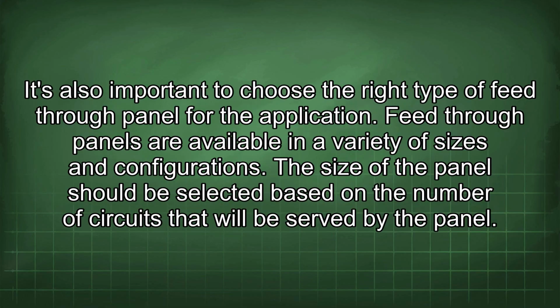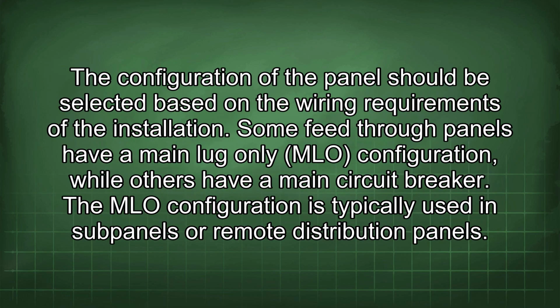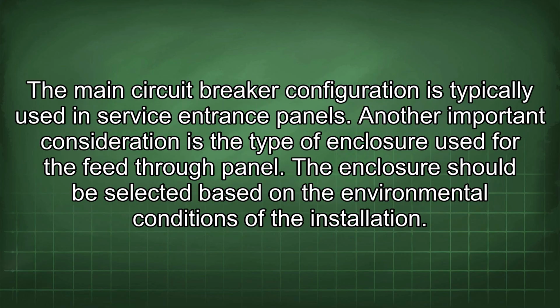It's also important to choose the right type of feed-through panel for the application. Feed-through panels are available in a variety of sizes and configurations. The size of the panel should be selected based on the number of circuits that will be served by the panel. The configuration of the panel should be selected based on the wiring requirements of the installation. Some feed-through panels have a main lug-only (MLO) configuration, while others have a main circuit breaker. The MLO configuration is typically used in subpanels or remote distribution panels. The main circuit breaker configuration is typically used in service entrance panels.